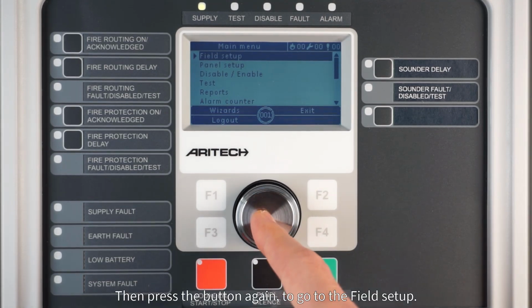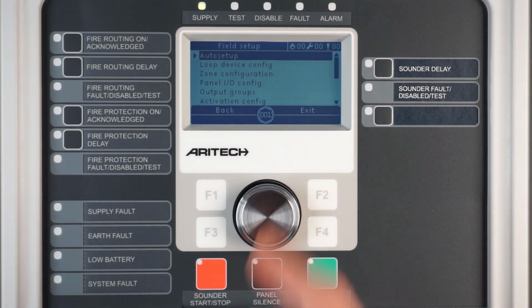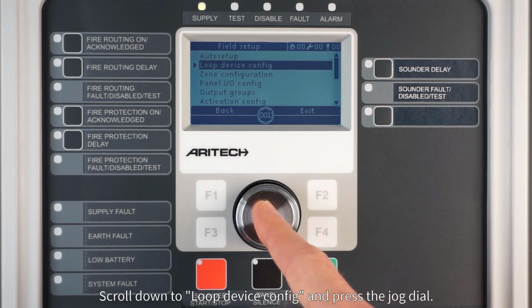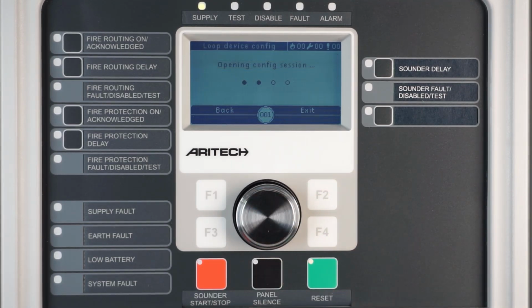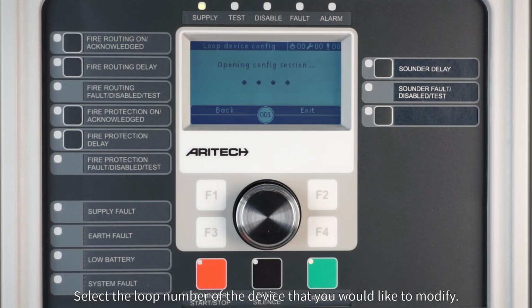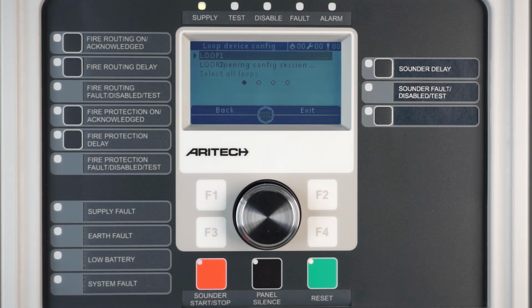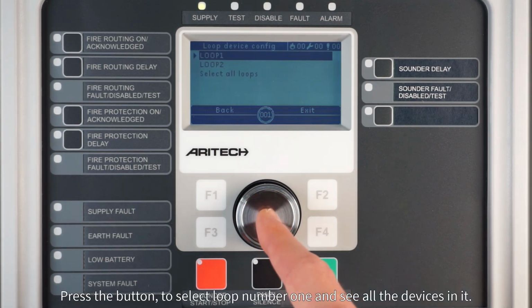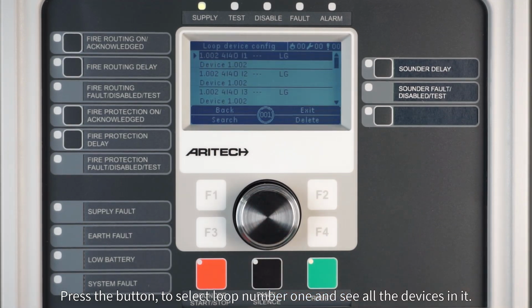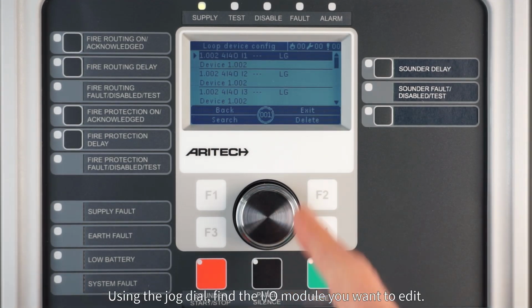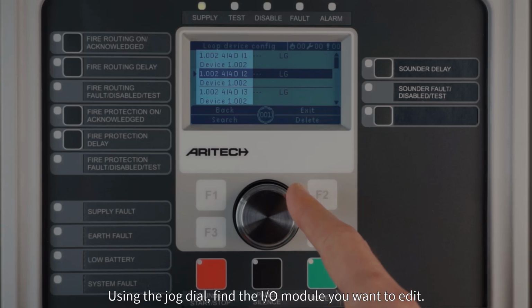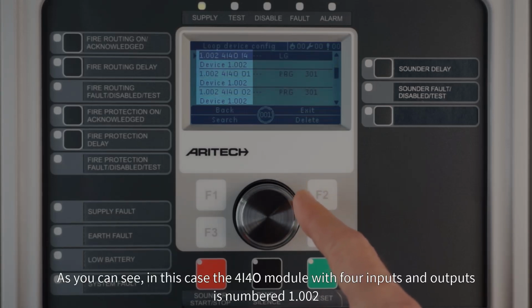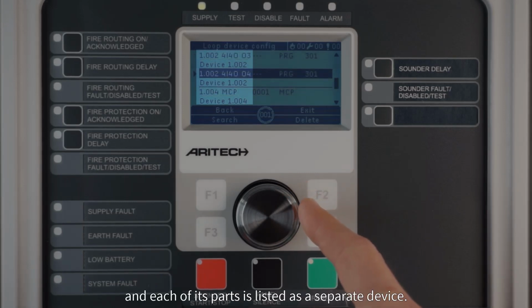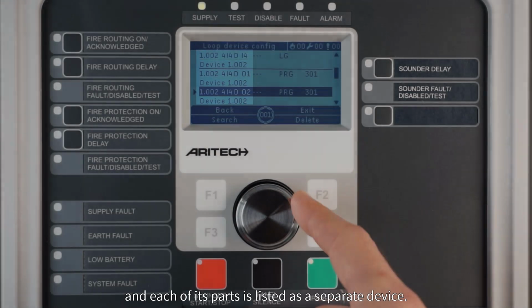Then press the button again to go to the field setup. Scroll down to loop device config and press the jog dial. Select the loop number of the device that you would like to modify. Press the button to select loop number 1 and see all the devices in it. Using the jog dial, find the I/O module you want to edit. As you can see, in this case the 4I4O module with 4 inputs and outputs is numbered 1002, and each of its parts is listed as a separate device.